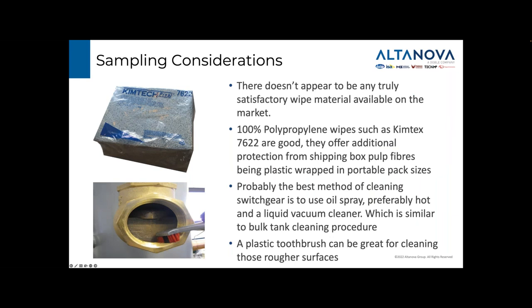Whilst there's no truly satisfactory wipe material on the market, wipes made from 100% polypropylene with low linting properties offer the best protection. Kimberly Clark produced a wipe called Kimtech 7622. It's individually packaged to prevent contamination of the wipes in storage and shipping boxes from cardboard, which contains wood pulp fibres. However, these wipes are not as robust as rags for cleaning rougher surfaces, so cleaning these areas can be supported with the use of a small nylon or polyester brush. A clean and dedicated toothbrush turns out to be quite great for this task.